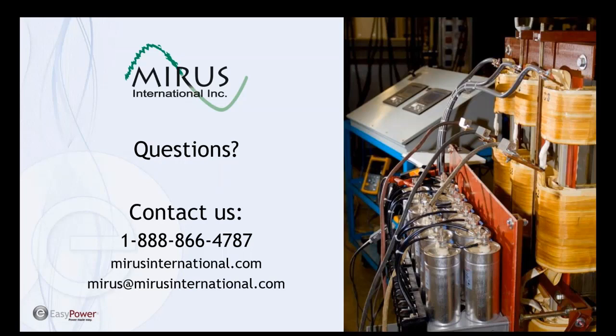What I do know is that if you use the SOLV computer simulation to generate the current spectrums, it will provide phase angles. So you'll get both the amplitude and the phase angle of the harmonic. And then using that, you can enter that into EasyPower to get the current injection you need. There also is, I believe, libraries within EasyPower of some nonlinear loads, and those libraries likely contain both the magnitude and phase angle.